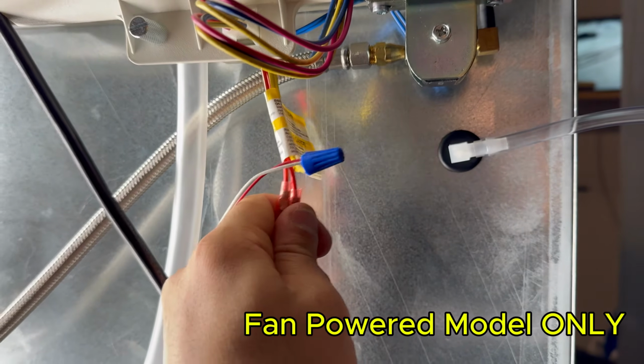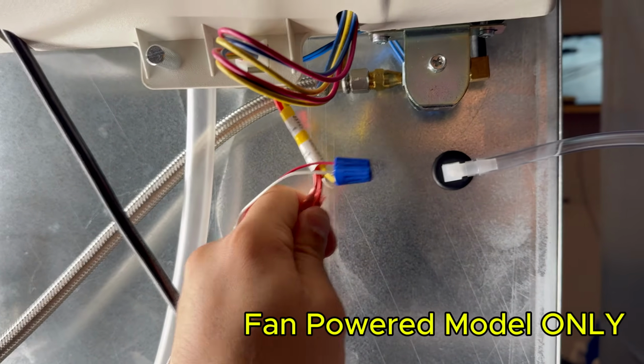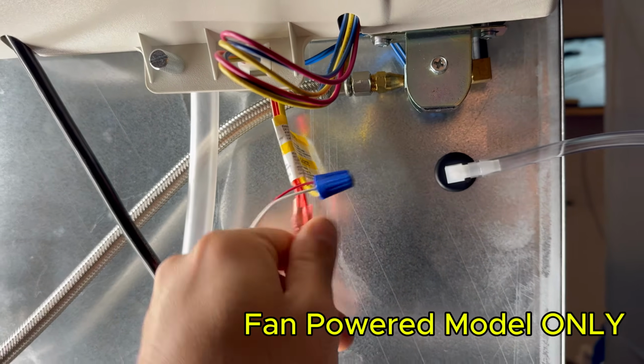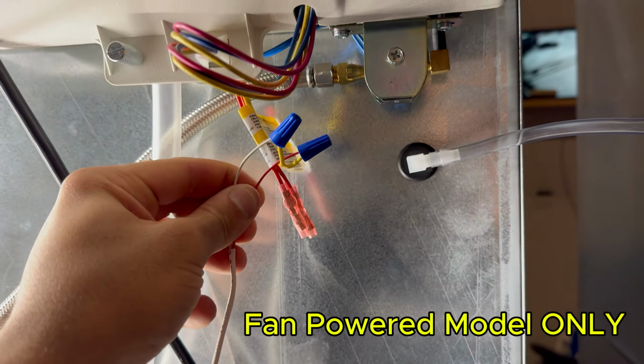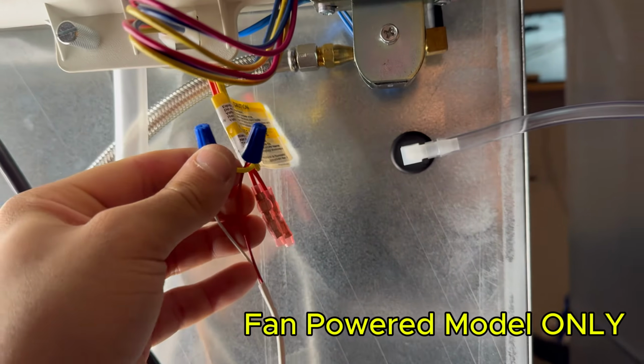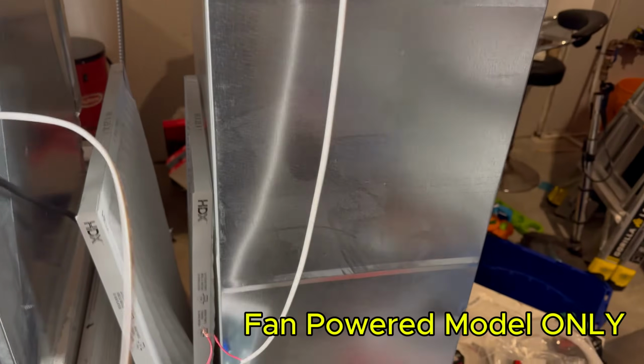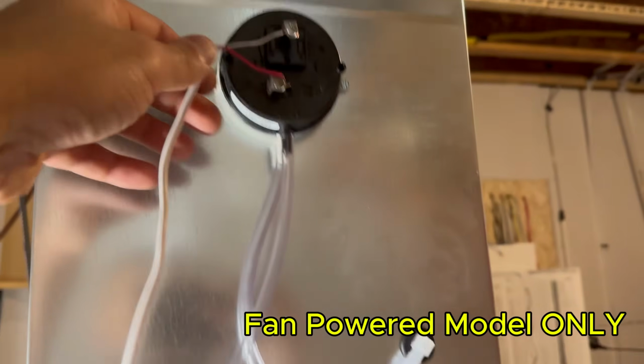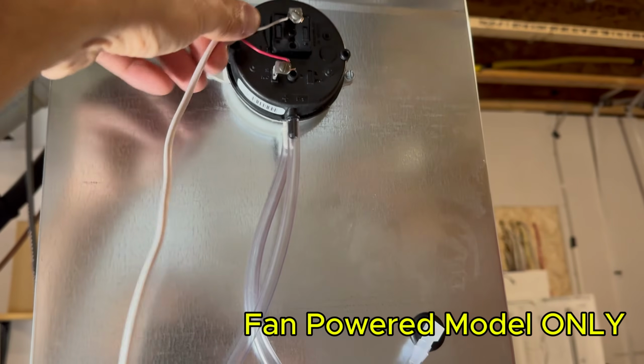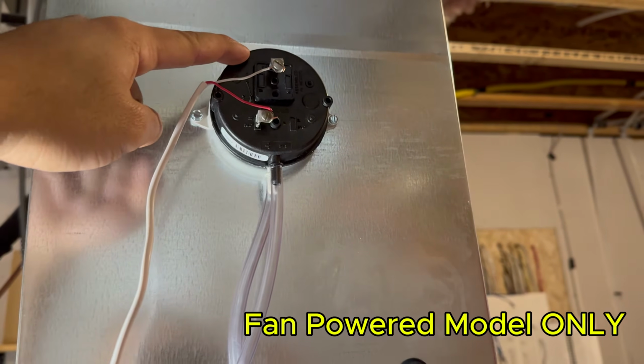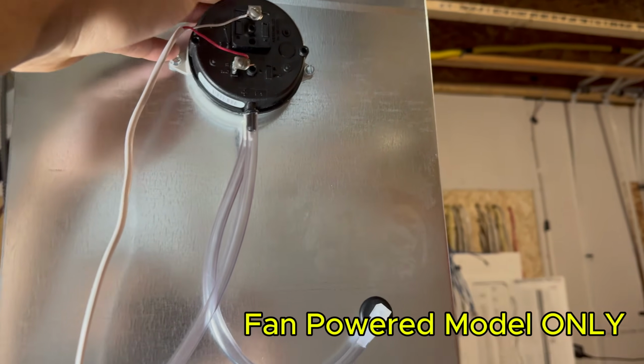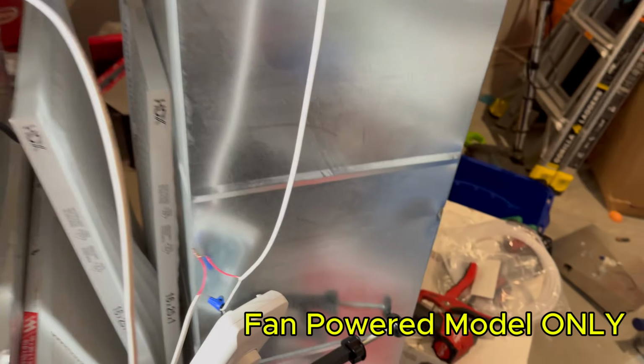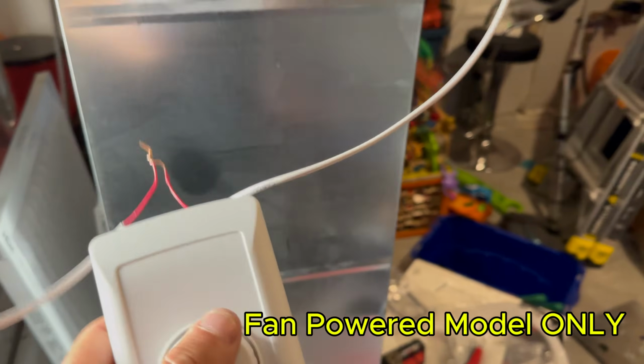We're not using these red ones. The red ones are not to be used when you're using an analog thermostat. So 1 strand of wire connects to these 2 yellow terminals. And on the other end, leave it. Don't touch it. Then you're going to have a 2nd strand of wire, the one we already connected to the pressure switch. So from here, we have it from the pressure switch, and on the other end, we're not going to touch it. But once we get to the humidistat, basically this is a switch.